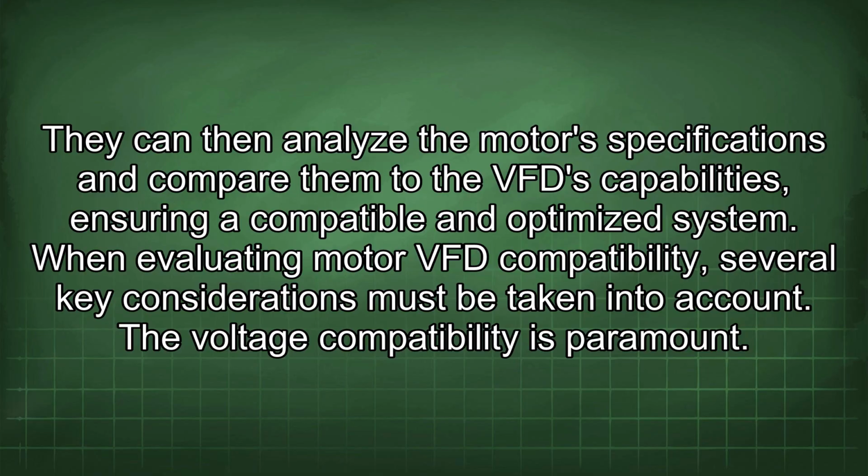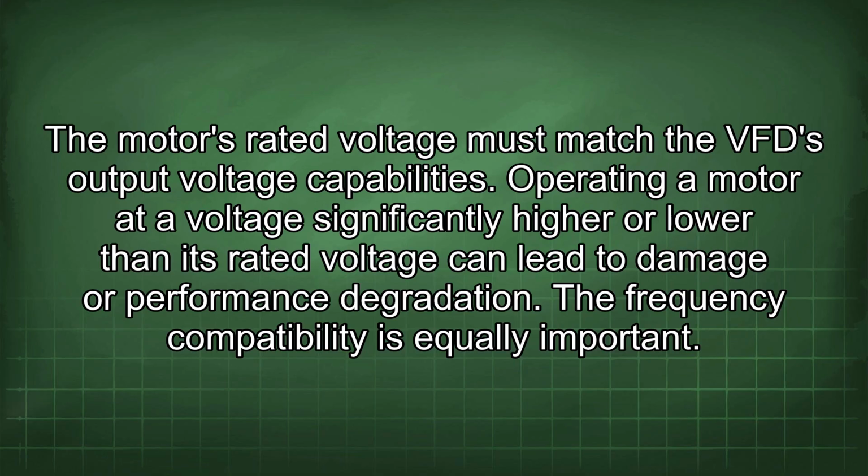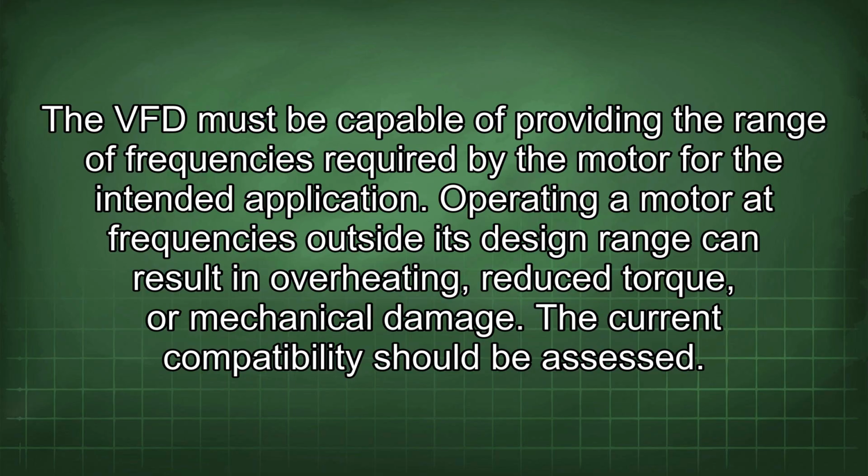When evaluating motor VFD compatibility, several key considerations must be taken into account. The voltage compatibility is paramount. The motor's rated voltage must match the VFD output voltage capabilities. Operating a motor at a voltage significantly higher or lower than its rated voltage can lead to damage or performance degradation. The frequency compatibility is equally important. The VFD must be capable of providing the range of frequencies required by the motor for the intended application. Operating a motor at frequencies outside its design range can result in overheating, reduced torque, or mechanical damage.